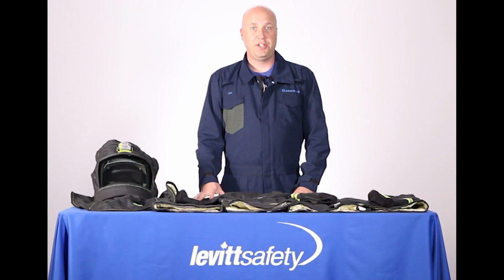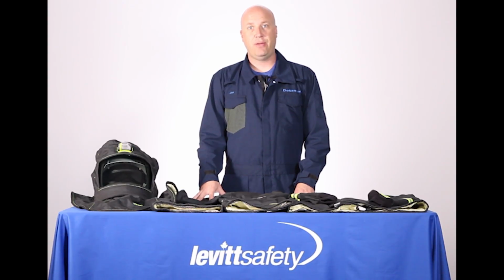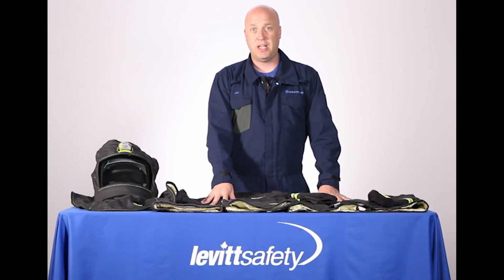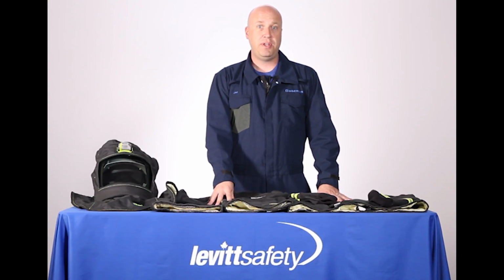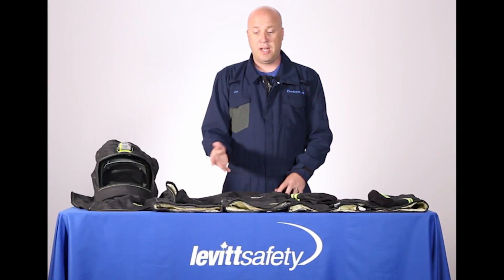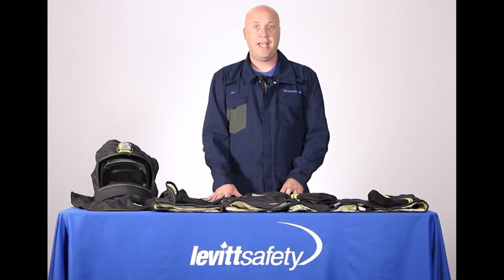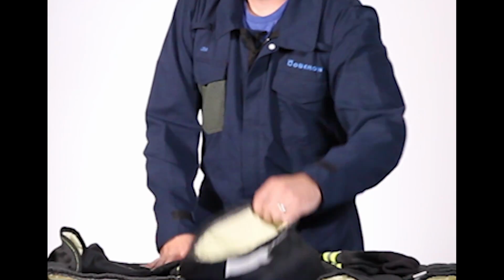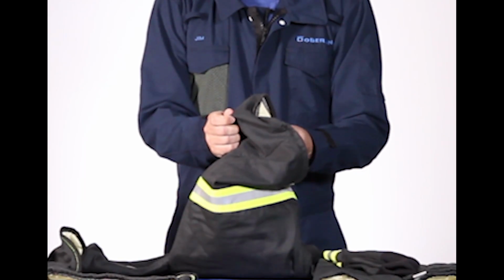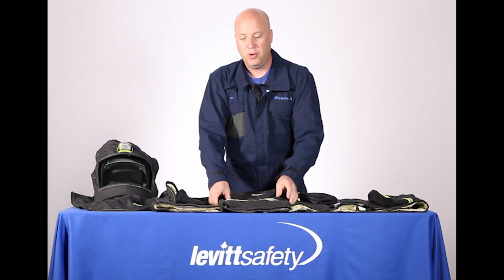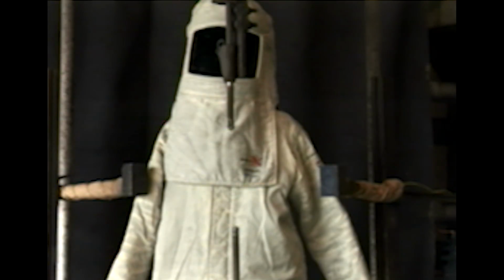Oberon arc flash suits are highly engineered and require special instructions for cleaning and repairs. Essentially, you want to keep your arc flash suit clean and dry. If you identify that it's contaminated with hydrocarbons or other materials that burn, you need to wash the materials before you can proceed to use the arc flash suit. If you identify that there's any repairs needed, you can't just sew this yourself. These highly engineered fabrics are multi-layer, and you must send the product back to the Oberon company for repairs. Oberon can replace a panel section of the arc flash suit or make the proper repairs so the suit remains compliant. If the arc flash suit is wet, that reduces your protection significantly.